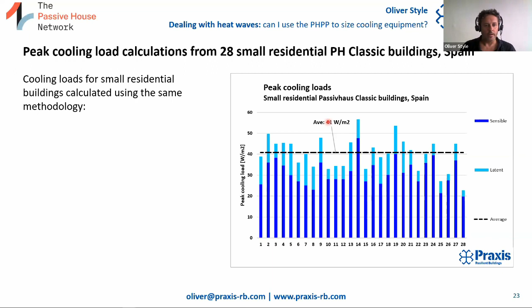This is obviously much higher than that value that came out of our PHPP for the certification, which was 12 watts per square meter. So basic conclusion, just be careful when you see that 12 watts per square meter or 13 or 14 on your PHPP verification page. Don't use that to size cooling equipment unless you want uncomfortable phone calls while you're on the beach during a heat wave and when you're on holiday.